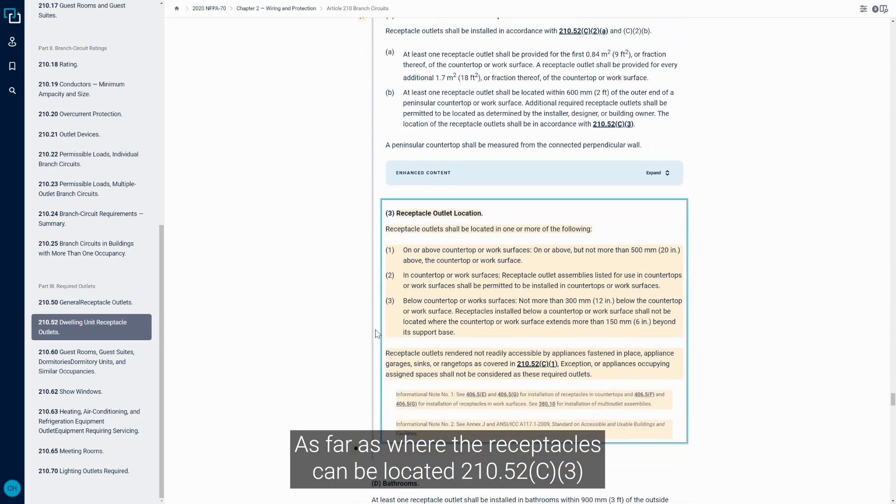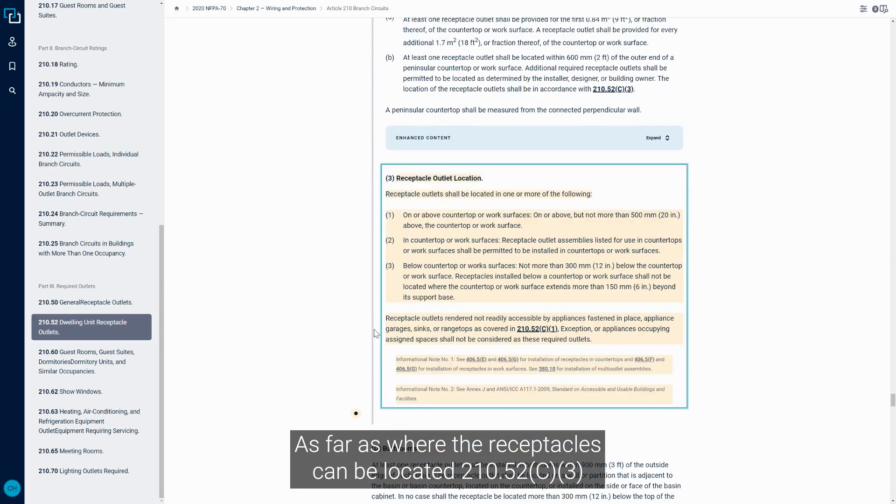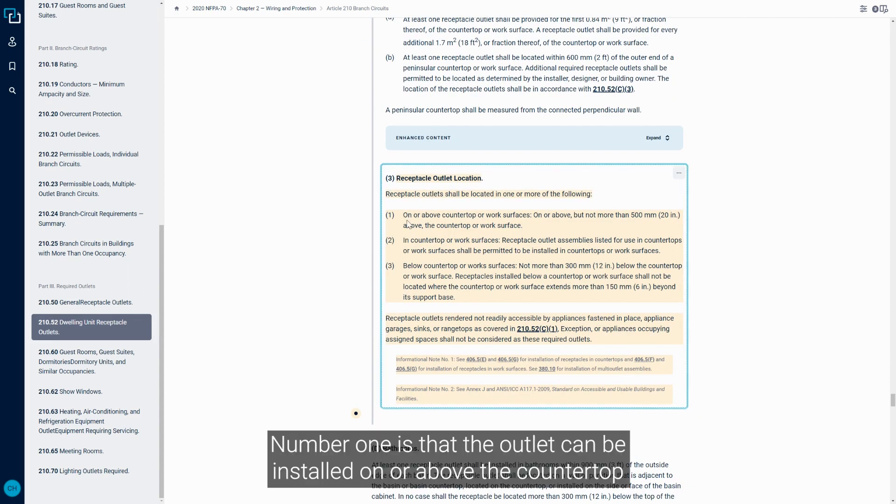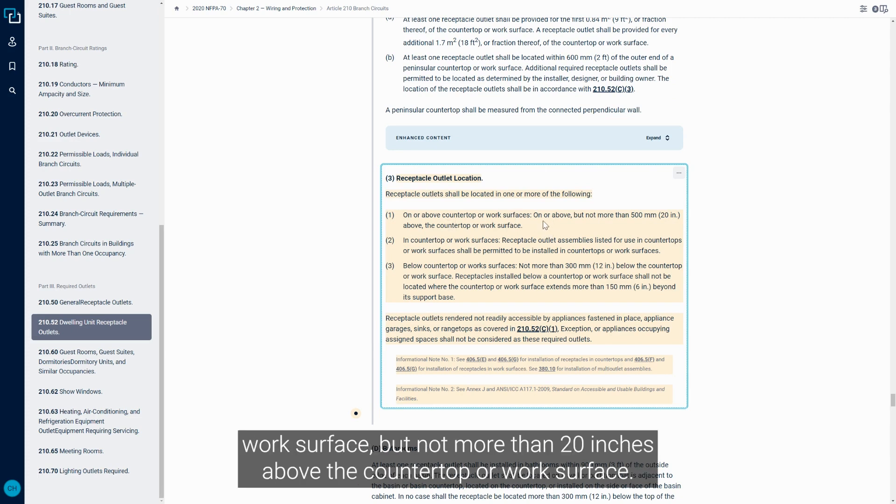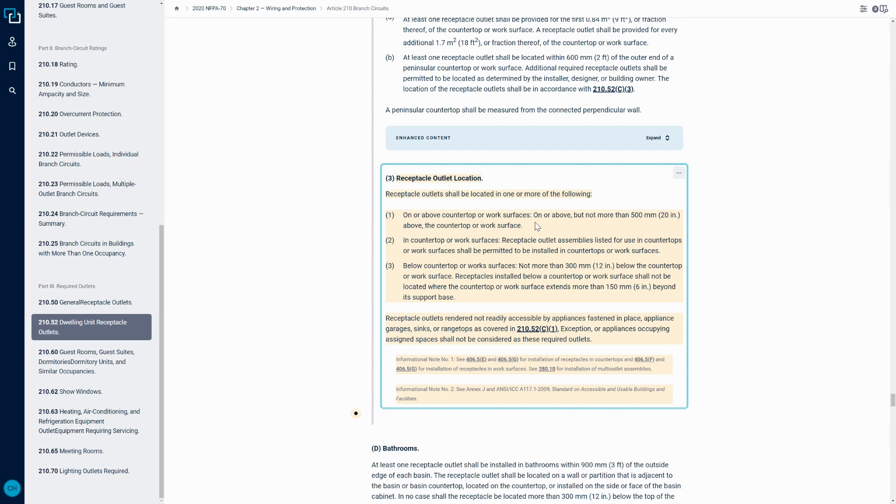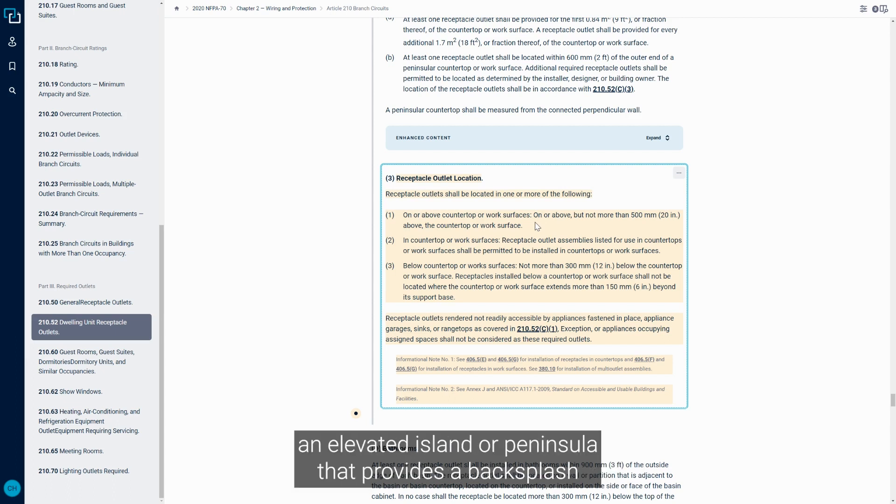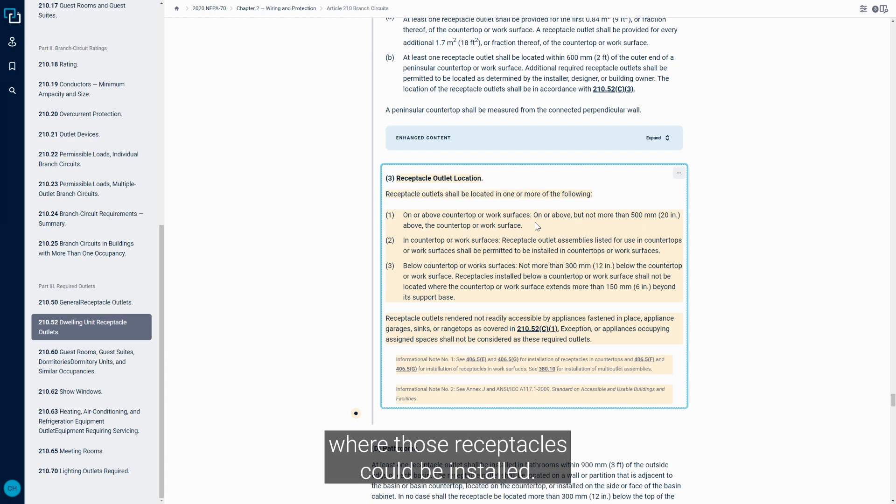As far as where the receptacles can be located, 210.52c3 gives us some options there. Number one is that the outlet can be installed on or above the countertop work surface, but not more than 20 inches above the countertop or work surface. So in this case, this would be where you could have like an elevated island or peninsula.